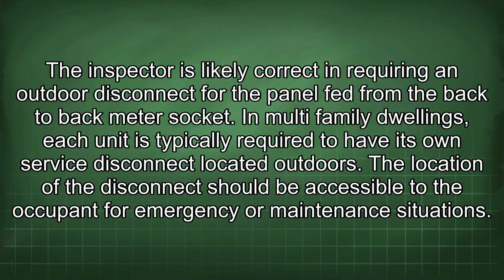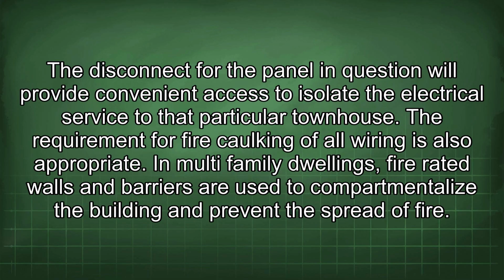The inspector is likely correct in requiring an outdoor disconnect for the panel fed from the back-to-back meter socket. In multi-family dwellings, each unit is typically required to have its own service disconnect located outdoors. The location of the disconnect should be accessible to the occupant for emergency or maintenance situations. The disconnect for the panel in question will provide convenient access to isolate the electrical service to that particular townhouse.